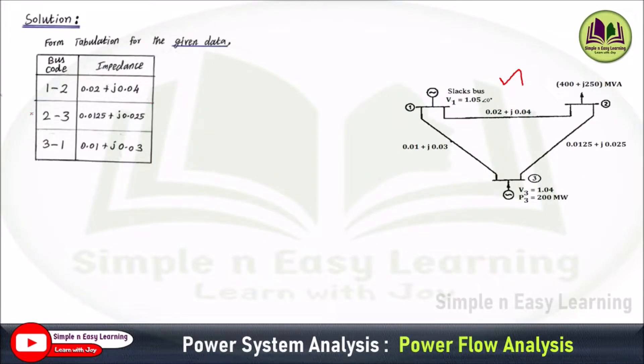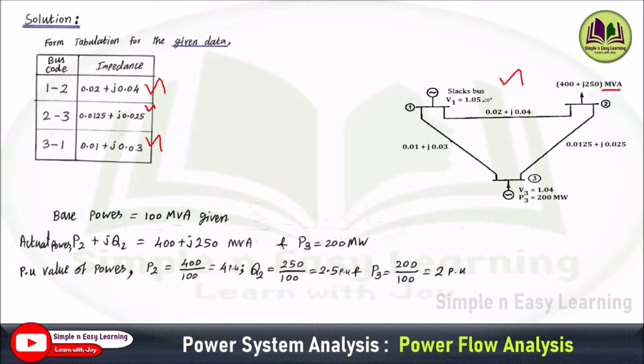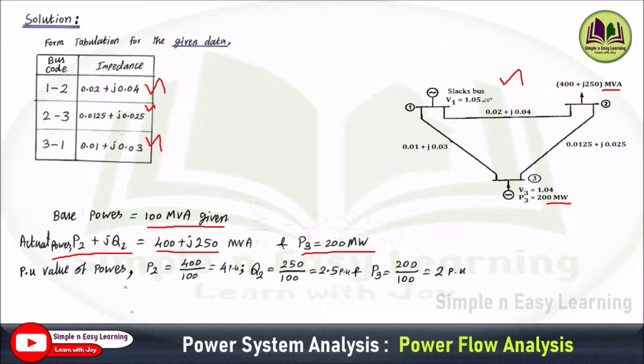From the given diagram, we make the bus data tabular column. Bus 1 to 2, bus 2 to 3, and bus 3 to 1 — all impedance values are specified in per unit. The power ratings are given in MVA and megawatt, so we convert these power ratings into per unit quantities. With a 100 MVA base, per unit equals actual value divided by base value. P2 plus JQ2 is 400 plus J250 MVA. So P2 equals 400/100 = 4 per unit, Q2 equals 250/100 = 2.5 per unit, and P3 equals 200/100 = 2 per unit. In the further steps, we use the per unit values only.